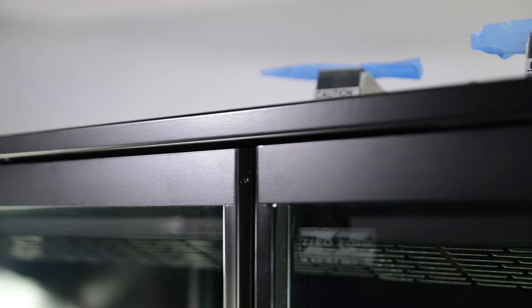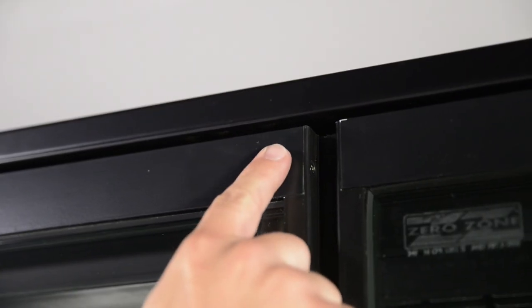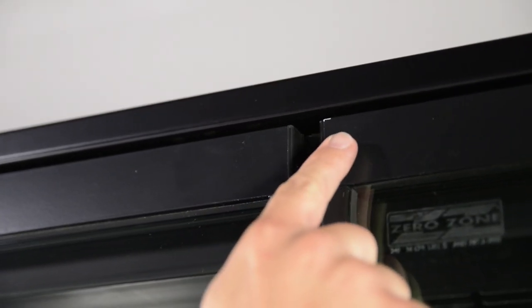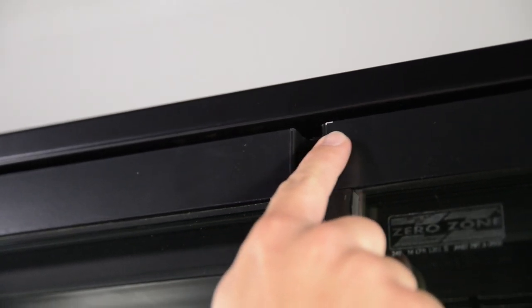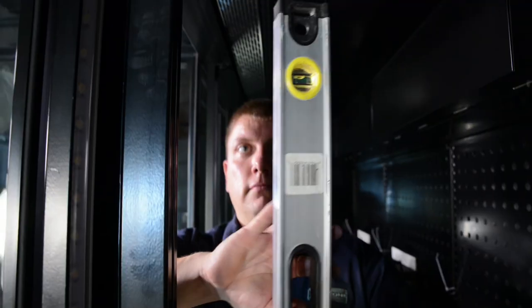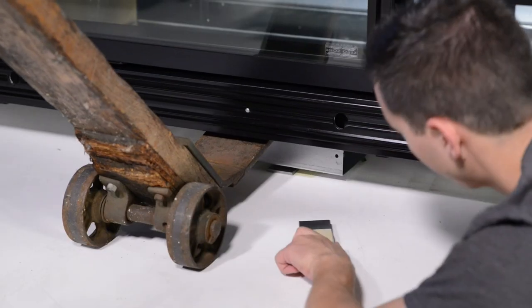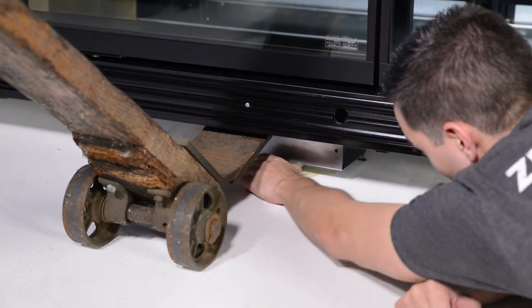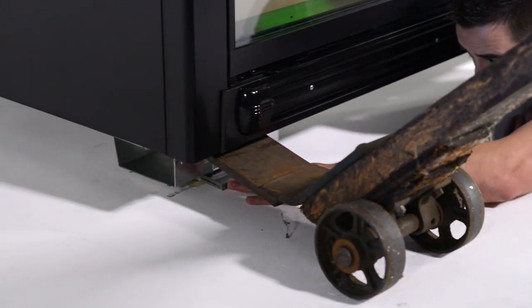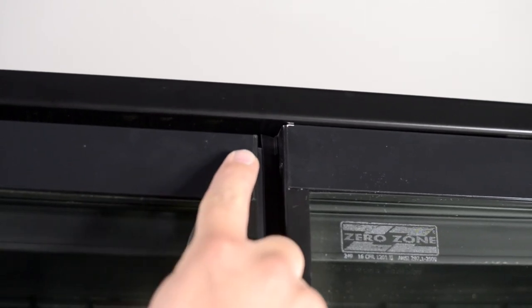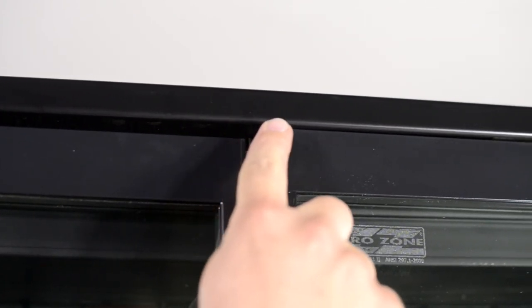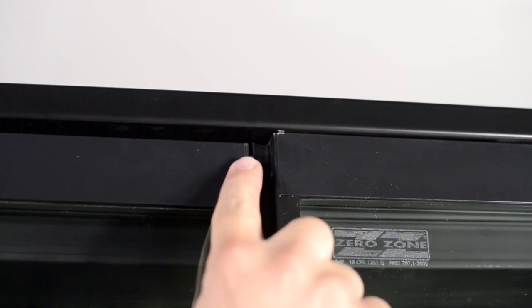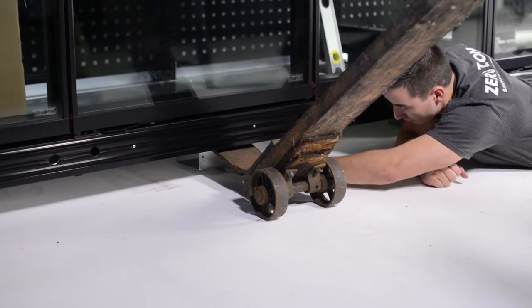At this point, the lineup should be plumb, level, and square. A visual indicator is that the door tops are level, meaning there is no sawtoothing. Be sure to use a four-foot level when checking case frame leveling. If the cases are not level, insert or remove shims under the front and rear base plates to ensure that the cases are set plumb, level, and square. Door sawtoothing is caused by the case being out of square or racked, making one end higher than the opposite end.